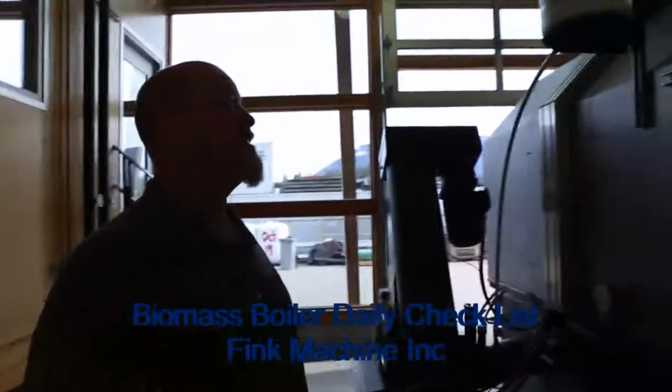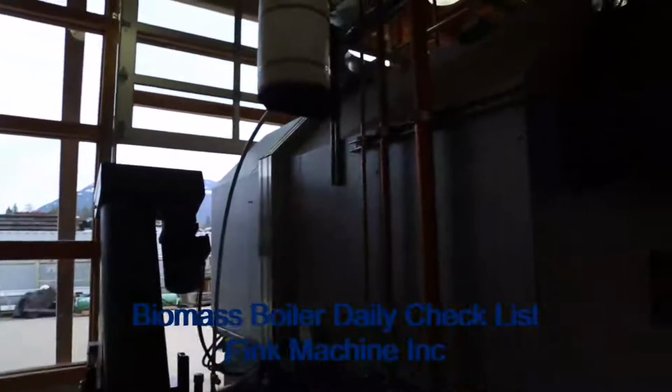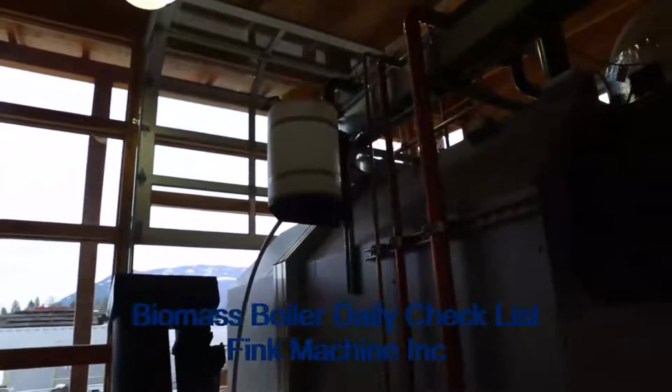As with any boiler, you're going to have a number of over-temperature devices, pressure relief valves, etc. We just want to take a look at those to see if anything is out of the ordinary. In this case, it all looks good.